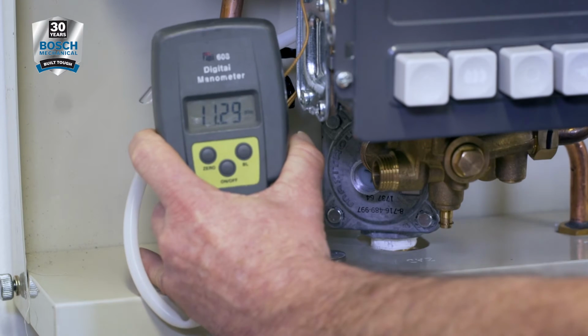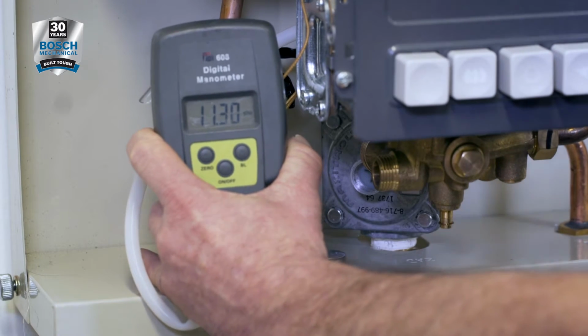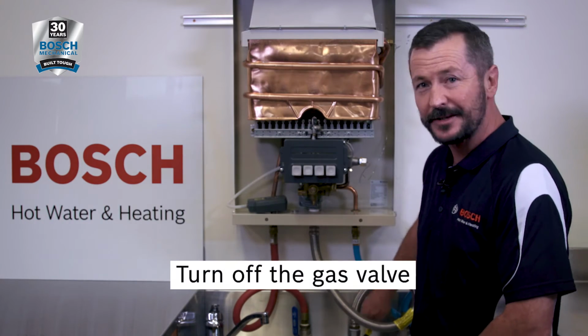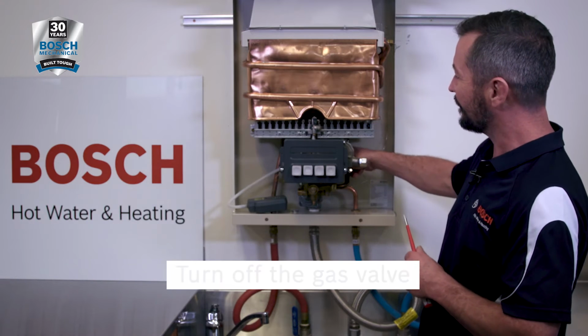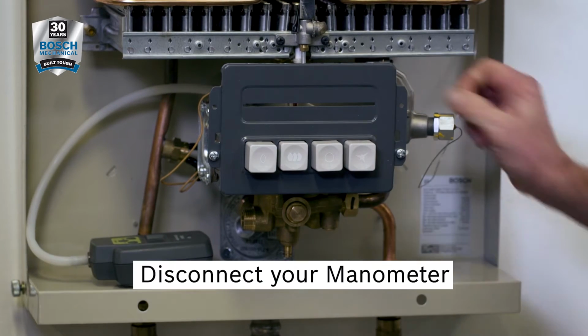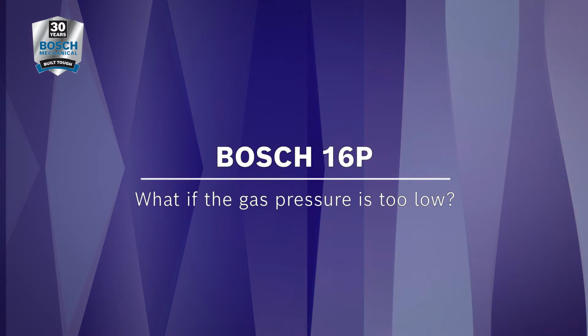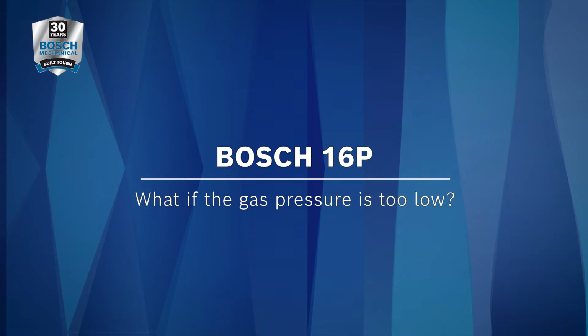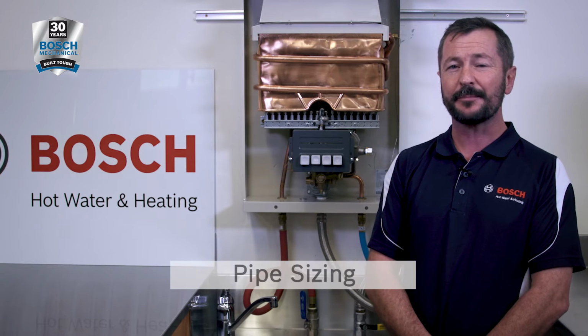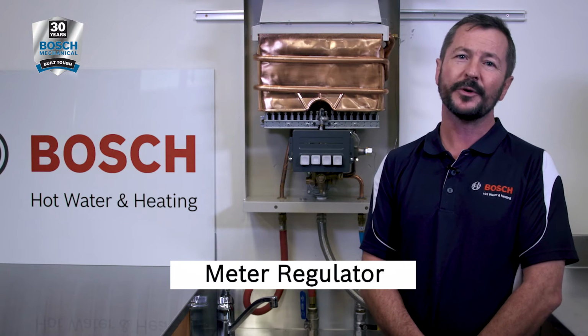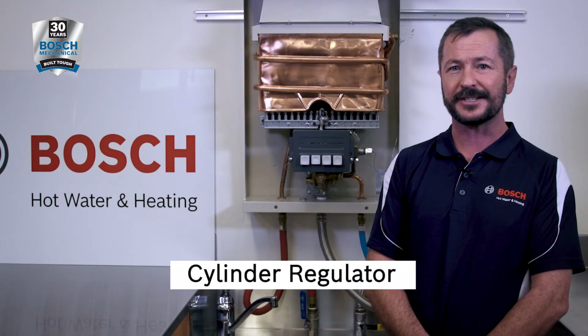Once our gas pressure is set, turn off the water to the appliance. Next, turn the gas valve off to the appliance, disconnect your manometer, and refit the sealing screw. If the gas pressure remains too low and can't be raised, this could indicate an issue with incorrect pipe sizing or an issue with your natural gas meter regulator or LPG cylinder regulator.